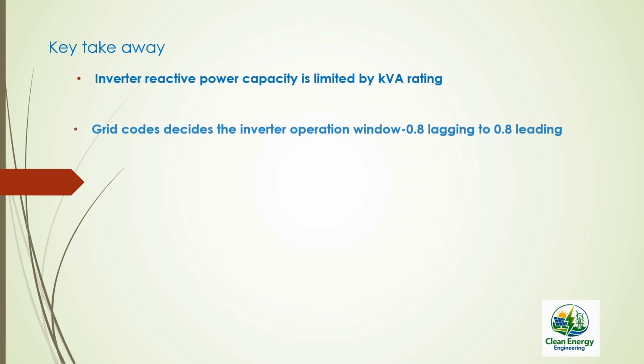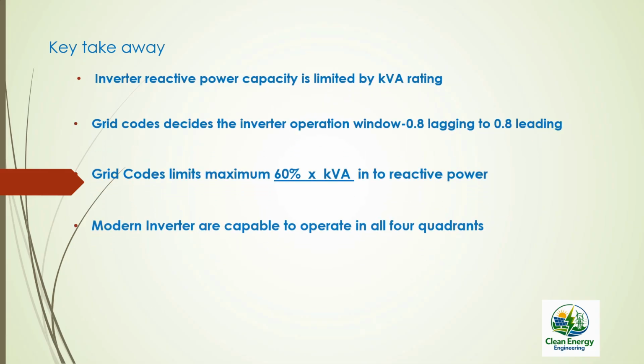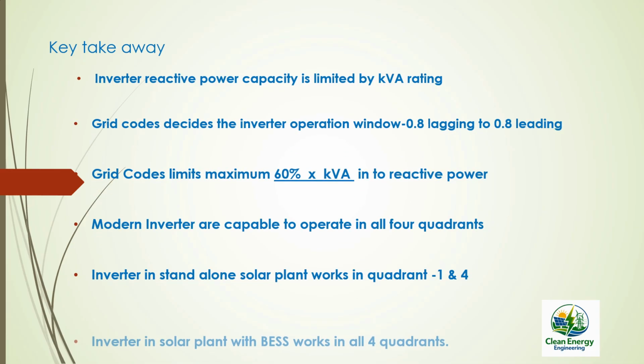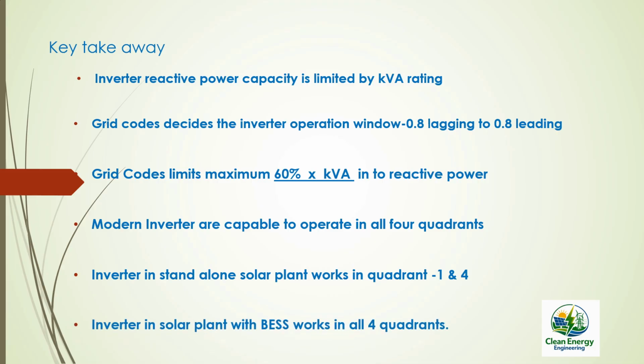Let's recap the key takeaways from today's video. Inverter reactive power capacity is limited by kVA rating. Grid codes decide the inverter operation window, which is generally 0.8 lagging to 0.8 leading. Grid code limits maximum 60% of inverter kVA rating as reactive power. Modern inverters are capable of operating in all 4 quadrants. An inverter in a standalone solar plant works in quadrant 1 and 4. An inverter in a solar plant with the BESS system works in all 4 quadrants.